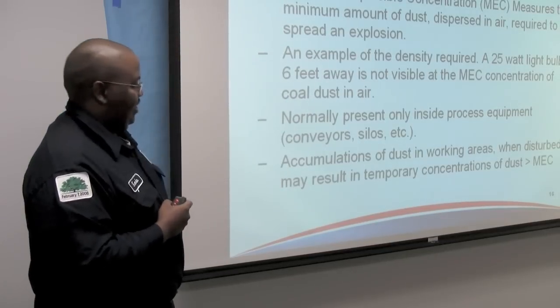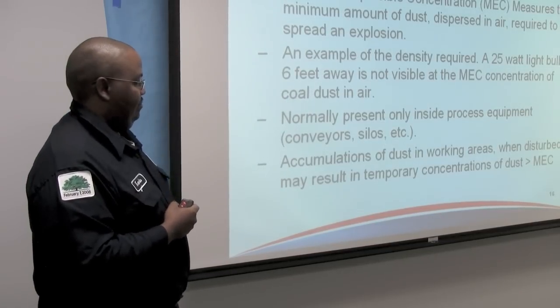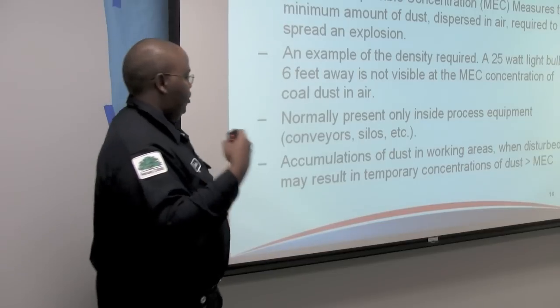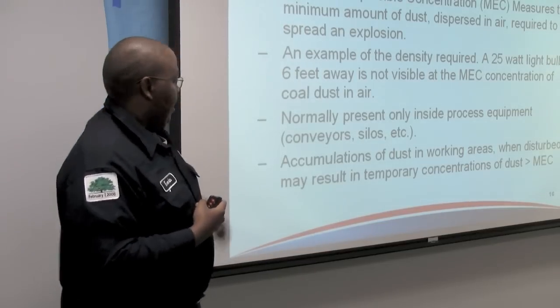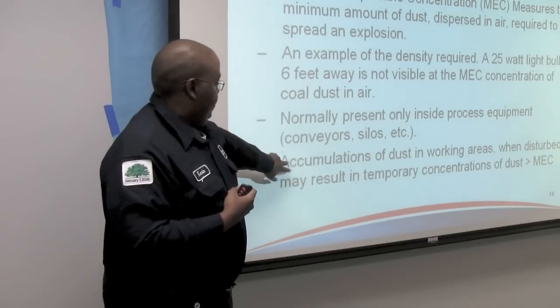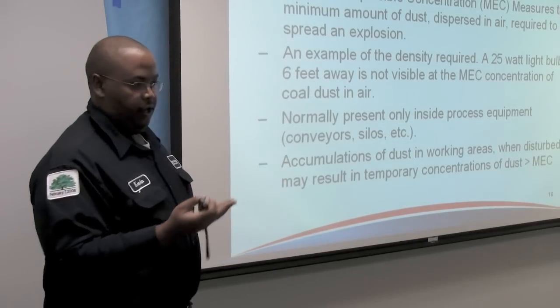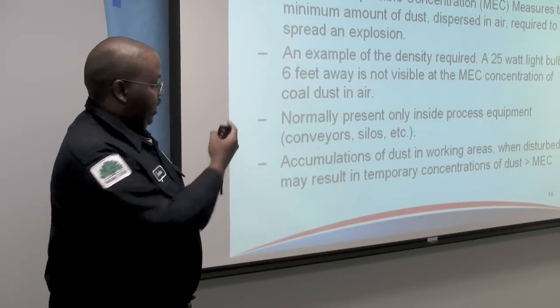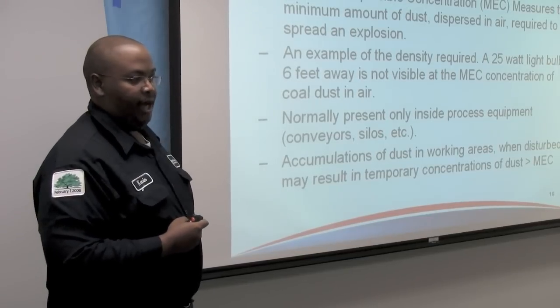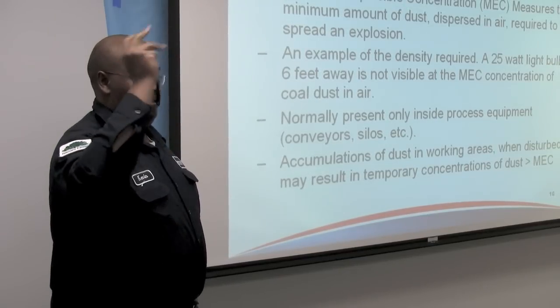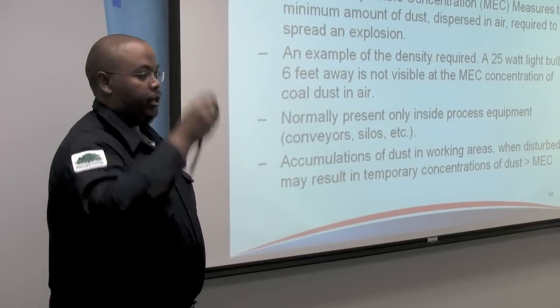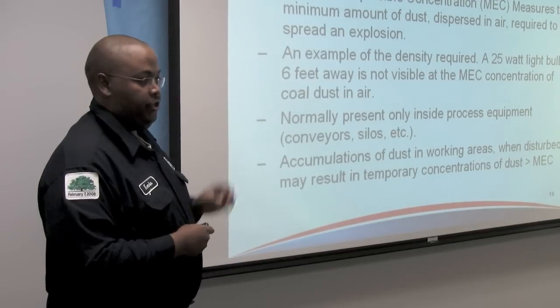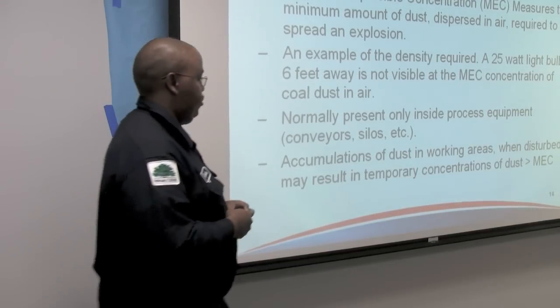MEC is normally present inside process equipment — your bulk bins, silos, things like that. Importantly, you can also have that minimum explosible concentration on rafters, beams, ductwork, and other places in your plant when you consider dust spread over an area. This is why housekeeping is extremely important.